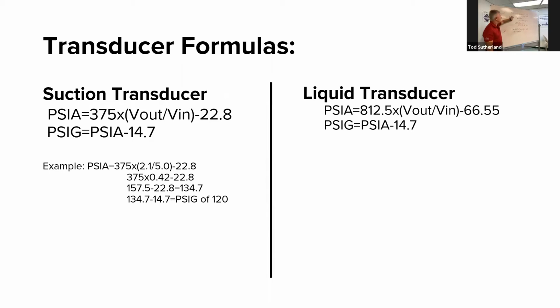Now, the only difference between the suction formula and the liquid formula is our numbers change. We calculate it the same way, except we go from 375 to 812.5 times voltage out over voltage in. Again, this is voltage out of the transducer, not the board. Voltage out of the transducer divided by the voltage coming into the transducer. And again, this is voltage DC, hint, hint, voltage DC, minus 66.55. So if we were to plug those same numbers into there, get our reading in atmospheric pressure, minus 14.7, that would tell you what your liquid pressure transducer is reading. And you would measure that against what you're reading on your liquid line. Any questions there?